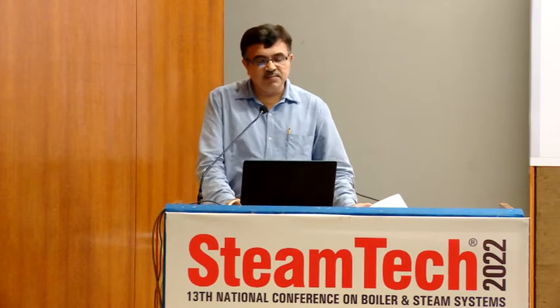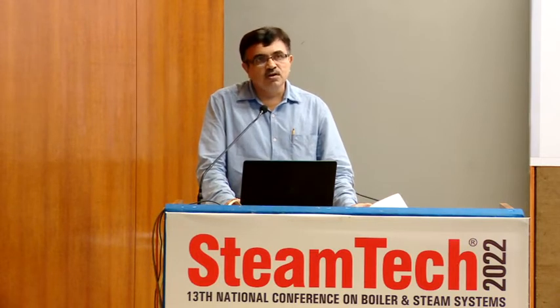However, the usage of a drone is not as simple as we think. There are a lot of challenges. Boilers present many challenges for flying, since the space within them is tight and full of objects, and the drone blades can be hit, so the drone can be damaged. So the simple drone that we see cannot be used for boiler inspection. Another thing is that the drone should be stabilized once it gets inside the internal part of the boiler. Stability is a big issue in the internal parts. Flying inside among the obstacles in the boiler is a big challenge for the drone, so a different kind of drone design is required.